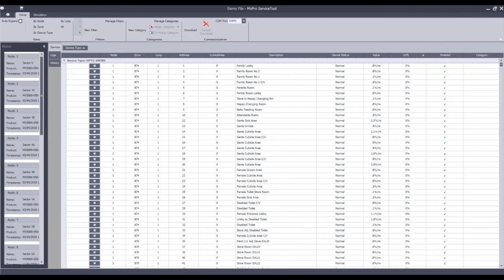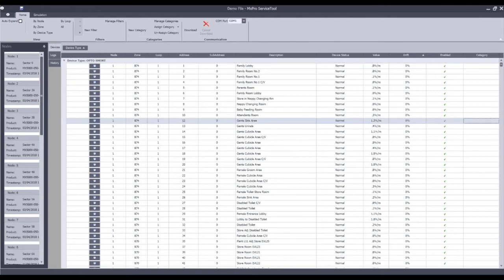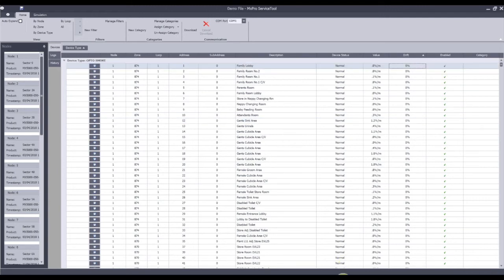These devices may at some point go into a pre-alarm as this value continues to rise. They may be flagged up through a category, so you could assign a custom category with a red colour so that you know at a glance that that device warrants attention. The drift value — if the device supports drift compensation, detail of which is available from the device manufacturers directly — is the device's way of saying that it has become contaminated through environmental factors over time and allows the panel to operate within those slightly expanded constraints. The device status on the right hand side shows enabled or disabled: a green tick indicates the device is enabled, a red cross indicates it was disabled.